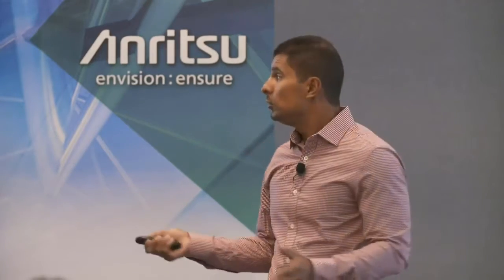They're like, no, it's 5 feet. It's right there. We visibly saw the antenna from the grandmaster. And we said, well, if you're only going 5 feet, your antenna delay is only a couple of nanoseconds at most. You just put in 4,000 nanoseconds.